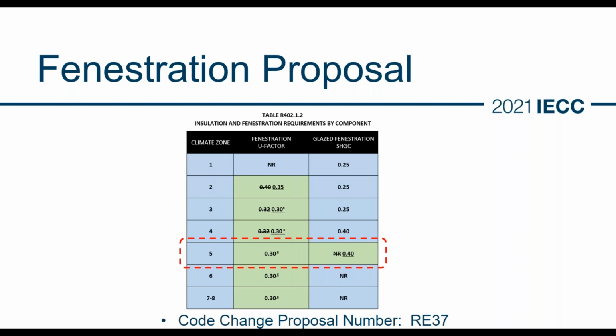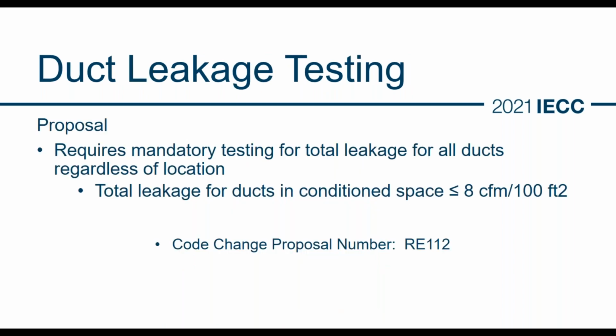So a lot of the windows on the market would already comply with this code requirement, but this does give you the ability to take credit for it when you're doing your ACCA Manual J heating and cooling load calculations, to reduce your air conditioning size. This is code change proposal number RE37, and again, it's another good one to take a very close look at. Connie, if you can go to the next slide, please.